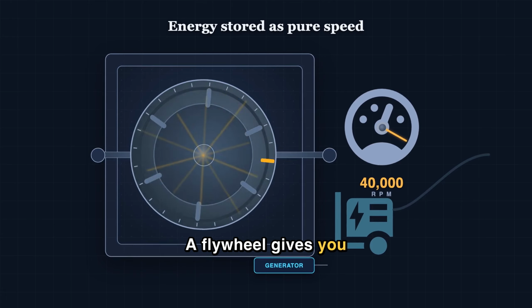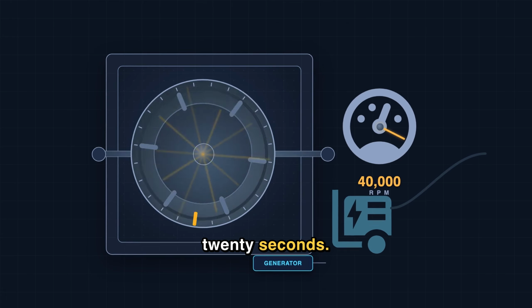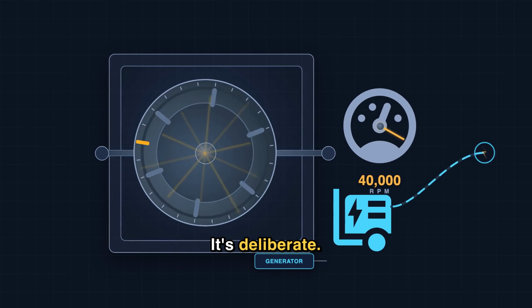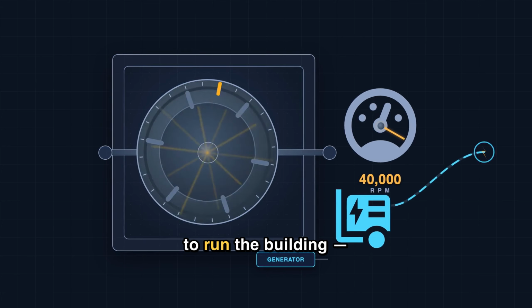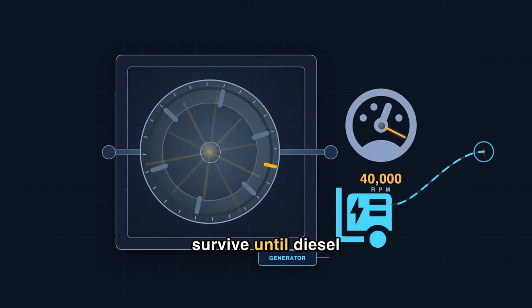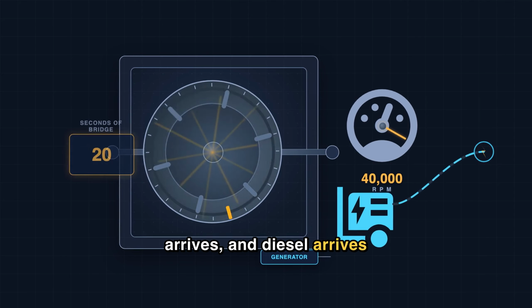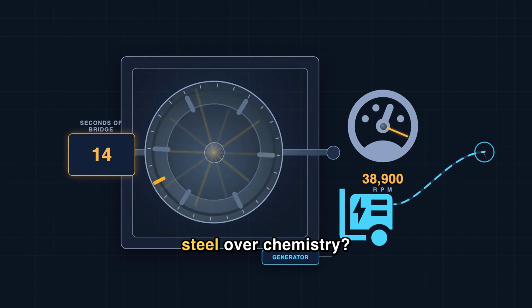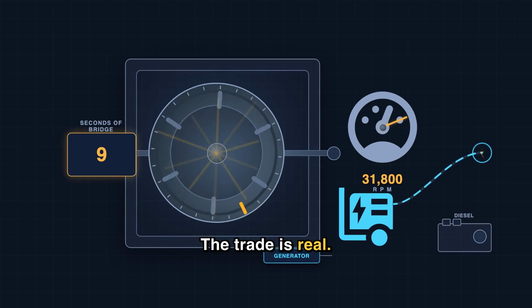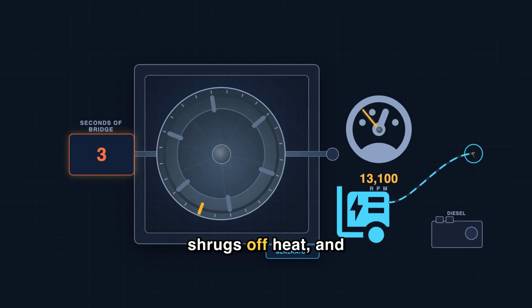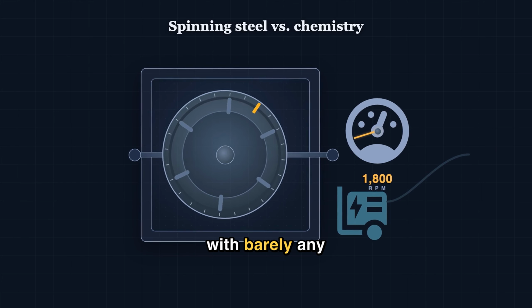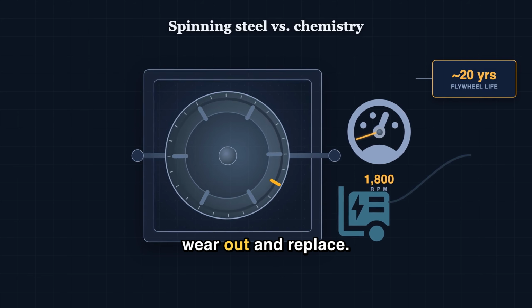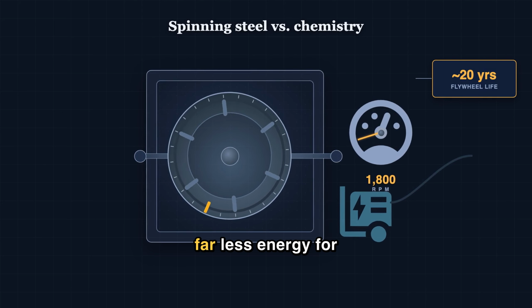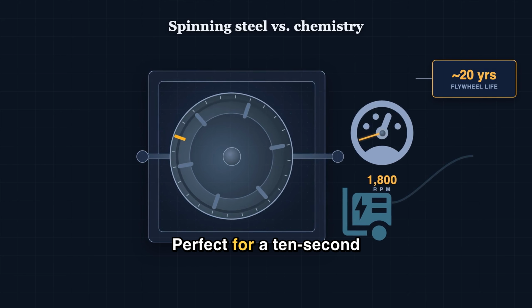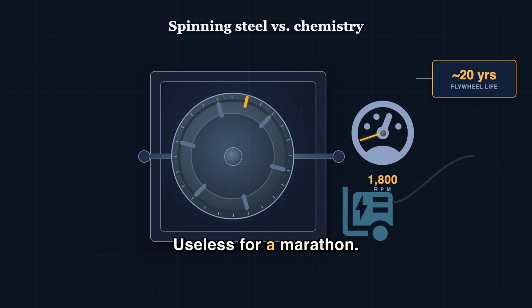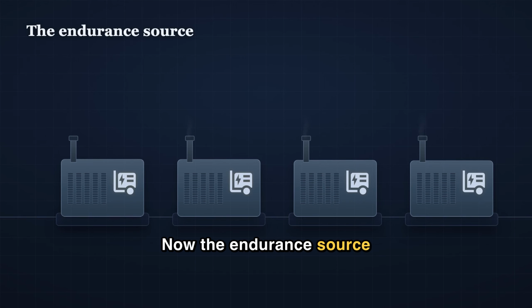Notice how long it lasts, though. A flywheel gives you only about 10 to 20 seconds. That sounds tiny. It's deliberate. A flywheel isn't trying to run the building. It only has to survive until diesel arrives, and diesel arrives in seconds. So I pick spinning steel over chemistry. The trade is real. A flywheel is compact, shrugs off heat, and lasts around 20 years with barely any maintenance, no cells to wear out and replace. The cost, it stores far less energy for its size. Perfect for a 10-second dash. Useless for a marathon.